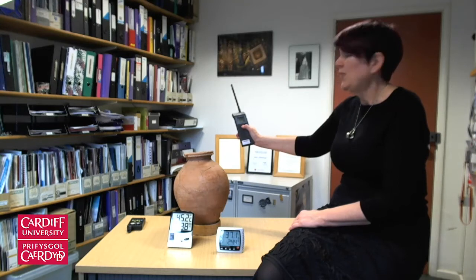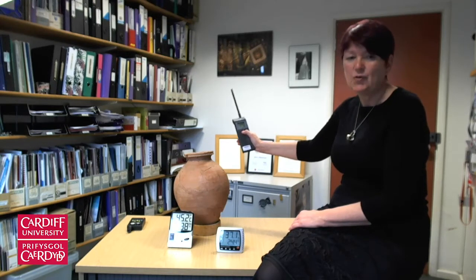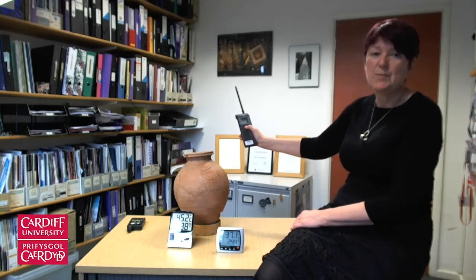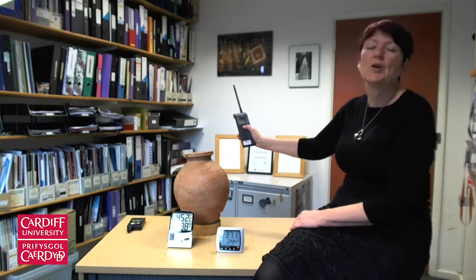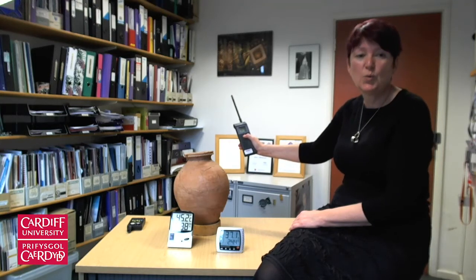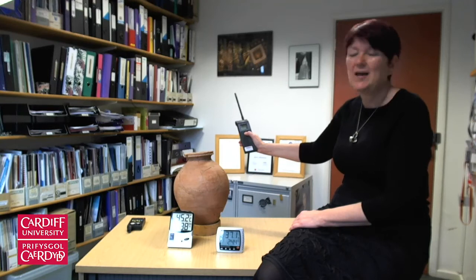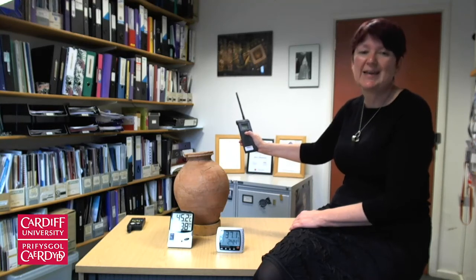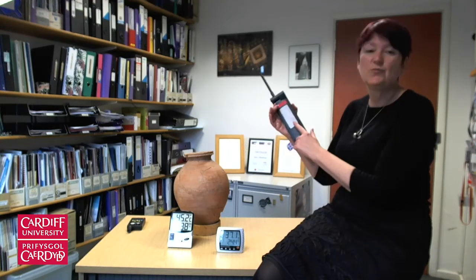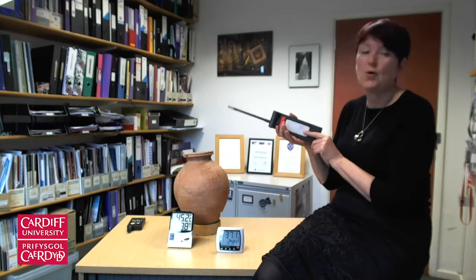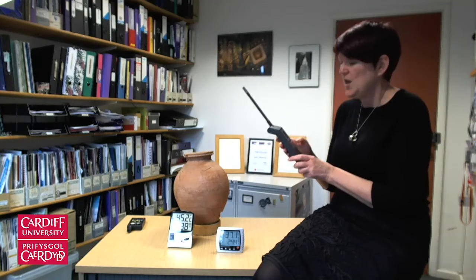With these pieces of equipment, the accuracy will be on the manufacturer's information, but remember that the accuracy only holds if you've calibrated the object, which means that you've checked it against a reliable source. We just write our calibration history on a sticker on the back of our logger. It's the easiest way. You don't need to adjust, you just need to record. So this is a simple one-off meter.